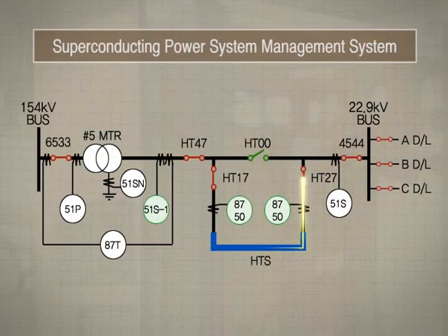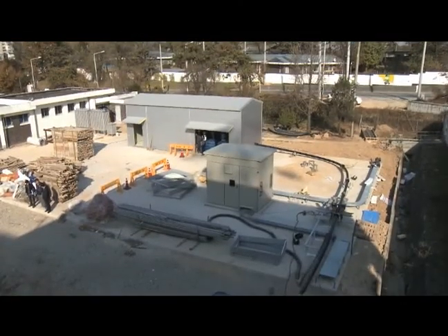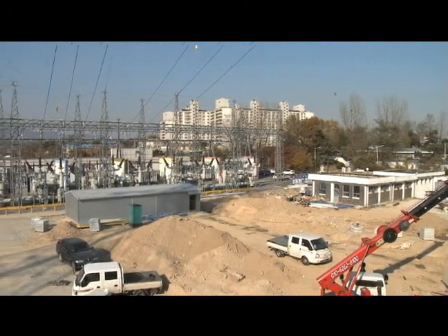The substation automation system is also used for remote monitoring and control of both the HTS cable and superconducting fault current limiter. When it is installed, it's possible to keep the power supply stable by using a bypass path if they have any problems.